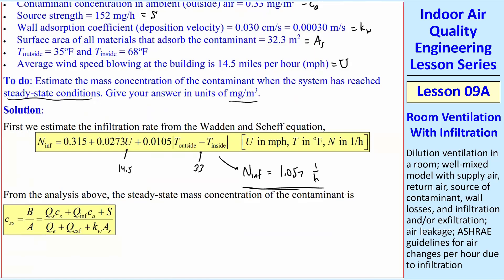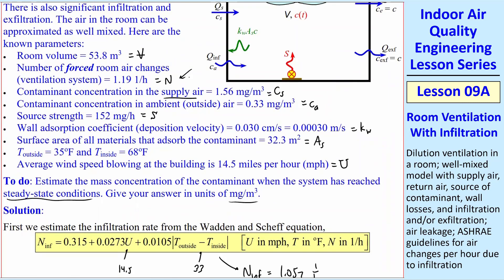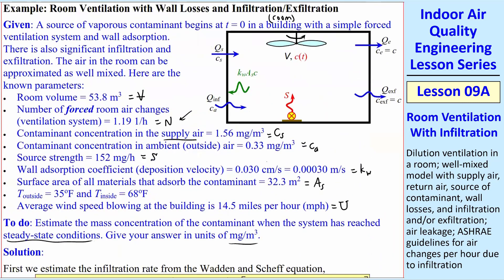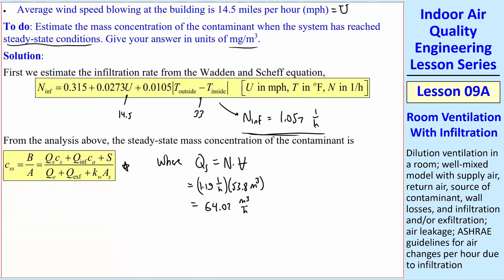Interestingly, in this case, 1.057 is pretty close to N itself. So you're putting almost the same amount of air forced in as you are getting naturally from the infiltration. We have to calculate Q_S is equal to N times V. And that turns out to be 1.19 per hour times 53.8 meter cubed. So that's equal to 64.02 meter cubed per hour.